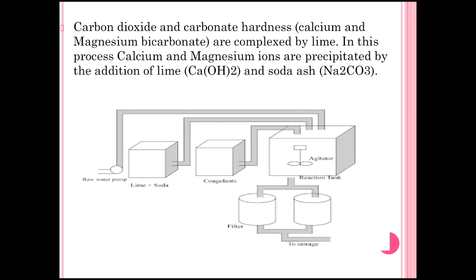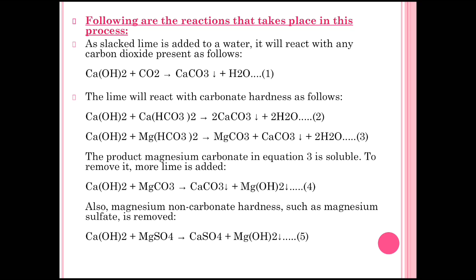Looking at the diagram of the soda lime process: there is first an inlet used to insert the raw water. From the left there is a box where lime plus soda is added, and another inlet for lime plus soda into the reaction tank. The third input is coagulants, used to coagulate all impurities. These chemicals are added in the reaction tank, then the water undergoes filtration so that carbonate and bicarbonate impurities are removed and water is converted into soft water.